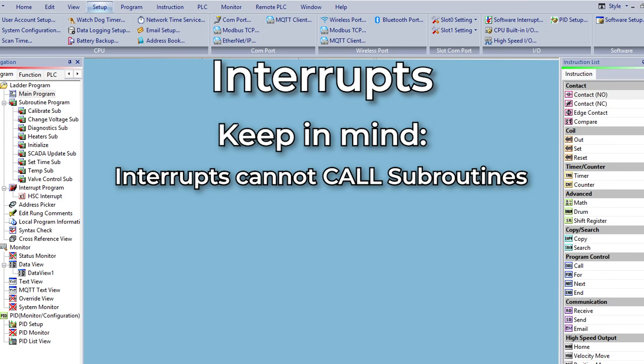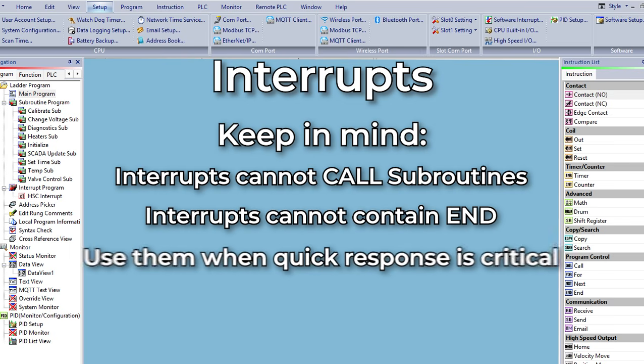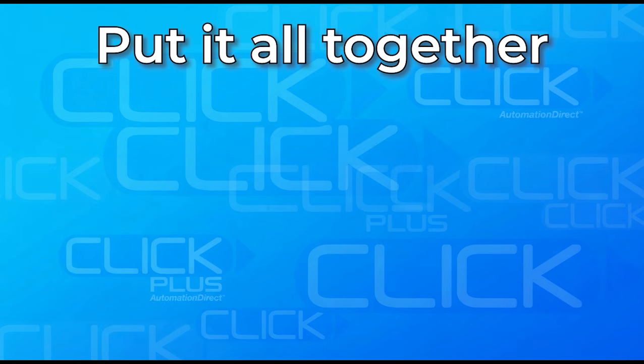Interrupts cannot call subroutines and do not use end. Reserve them for anything that absolutely cannot wait for the next full scan. Counting fast encoder pulses without missing counts, updating a PID loop on a precise schedule, or reacting instantly to a crucial limit switch.